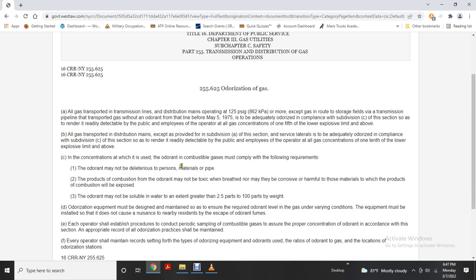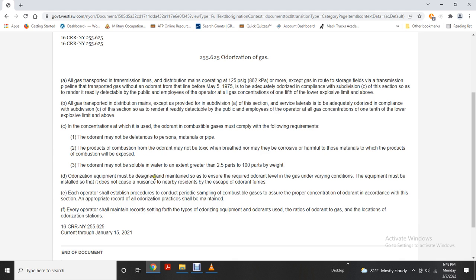The odorants may not be deleterious to the person or the material of the pipe. Products of combustion of the odorant may not be toxic when breathed. Nor may they be corrosive or harmful to the material to which the products of combustion will be exposed. The odorant may not be soluble in water to an extent greater than 2.5 parts to 100 parts by weight. Odorization equipment must be designed to maintain and ensure the required odorant level of the gas under various conditions. Equipment must be installed by a design that does not cause nuisance to nearby residents by escaping odorant fumes.